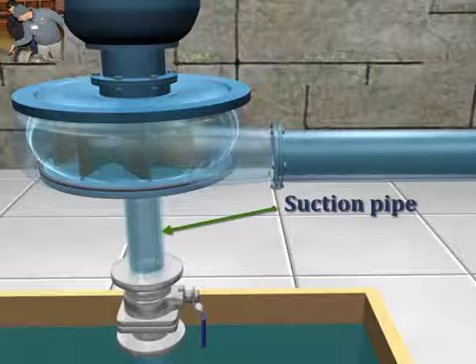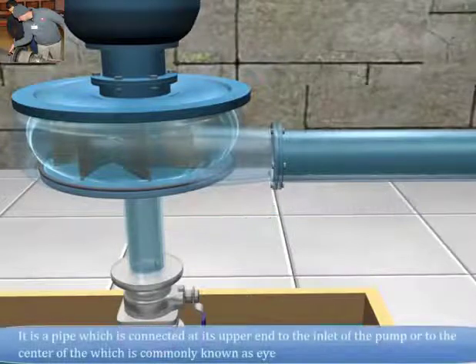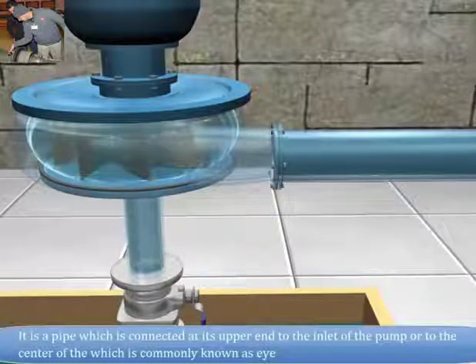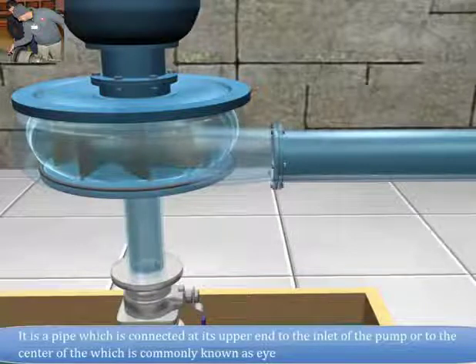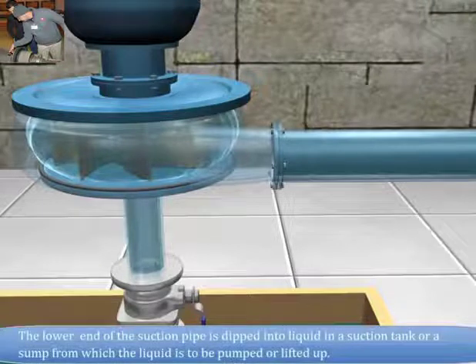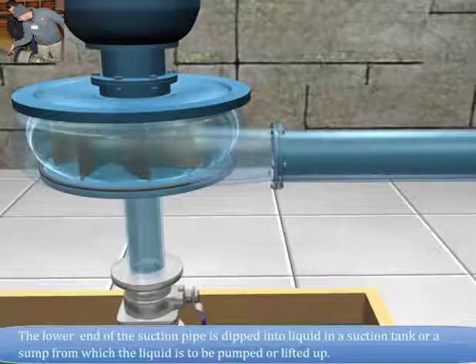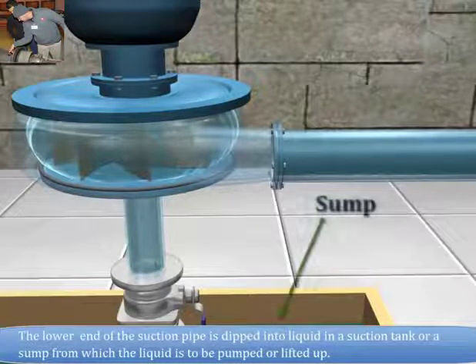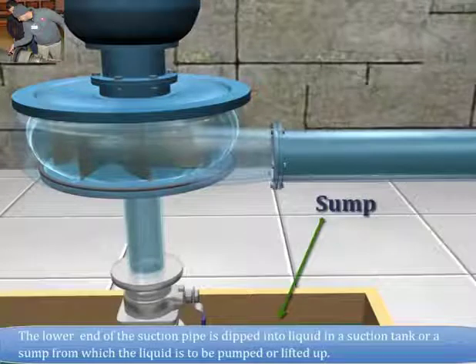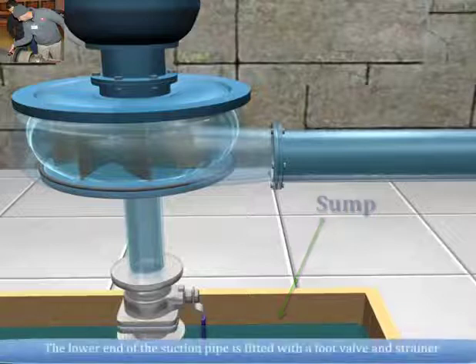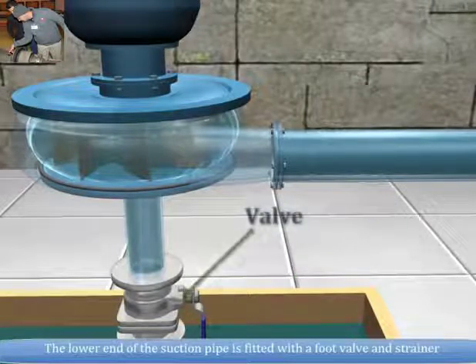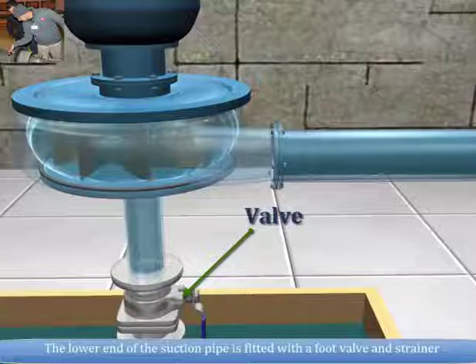Suction pipe. It is a pipe which is connected at its upper end to the inlet of the pump or to the center which is commonly known as eye. The lower end of the suction pipe is dipped into liquid in a suction tank or a sump, from which the liquid is to be pumped or lifted up. The lower end of the suction pipe is fitted with a foot valve and strainer.